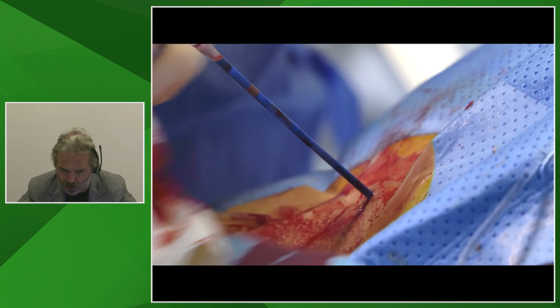So the main contraindications are severe calcification and a reference vessel that is below 6. The point is that when you have a large tortuosity, a calcified vessel with a reference vessel that is below 6, and you go with the 18 French compatible MANTA, it's better to skip to another device. But when you stay in the range of the indication, this is the only device that has a CE mark for closing up to 24 French. So in my experience, the results are excellent.